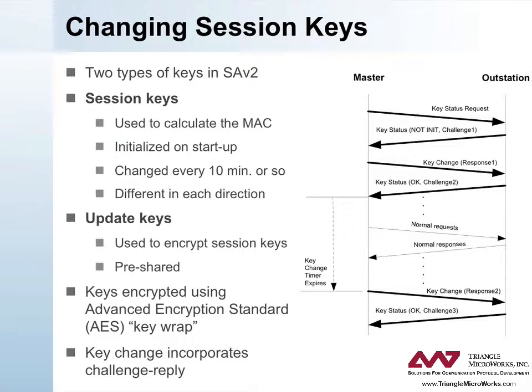Distribution SCADA systems using dial-up and gathering data every hour or every day would naturally change session keys much less frequently, perhaps once a week. The specification states that session keys may be renewed either when a configured interval has passed or when a configured number of messages have been exchanged. There are two session keys used, one in each direction.